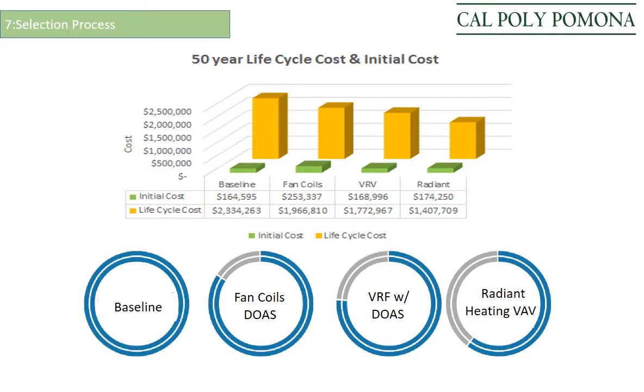The variable refrigerant volume initial cost was 168,000. This is lower than the fan coils because it did not require boilers. Its lifecycle cost was 1.7 million. Radiant floor heating had one of the lowest initial costs at $174,000 and the lowest lifecycle cost at 1.4 million. This makes the radiant floor heating very appealing.